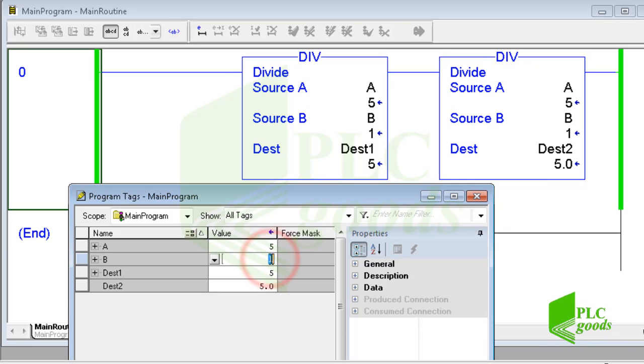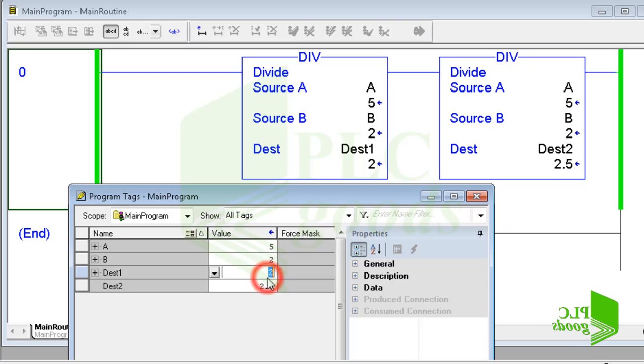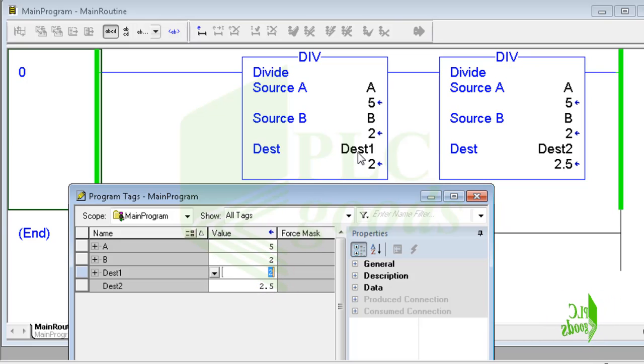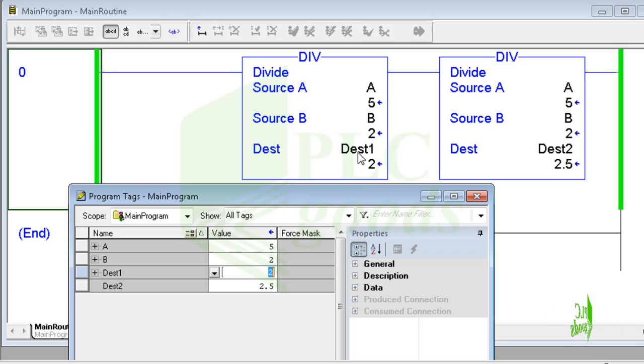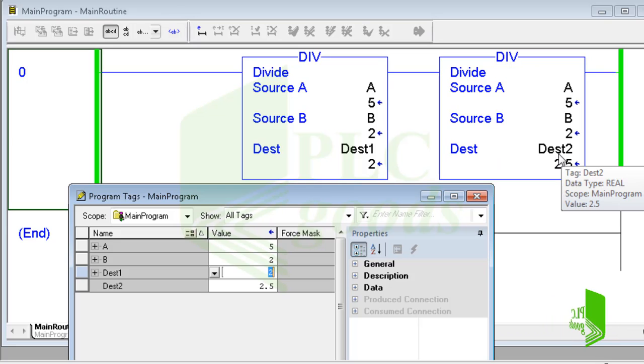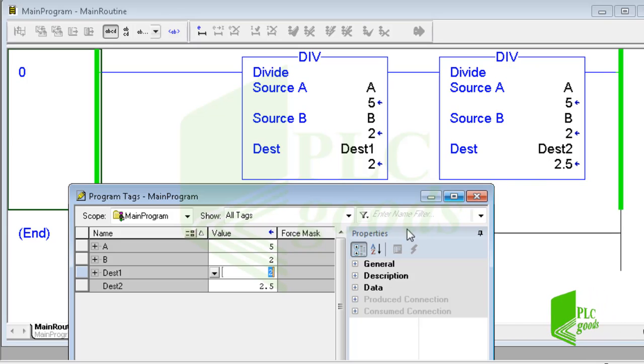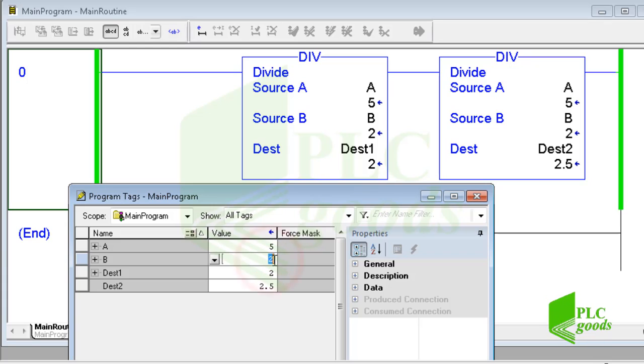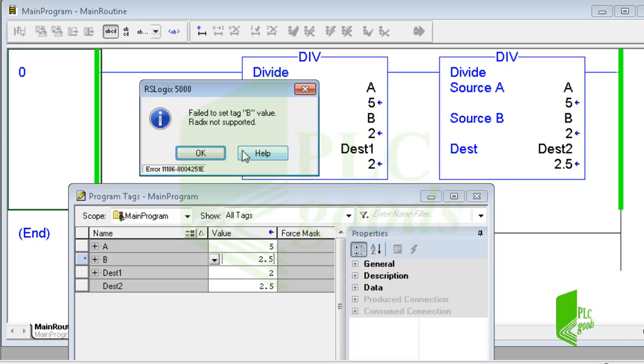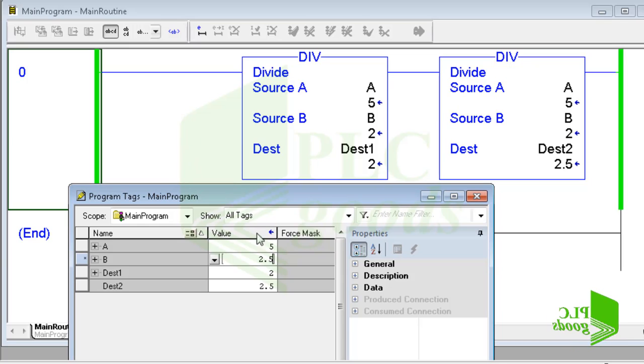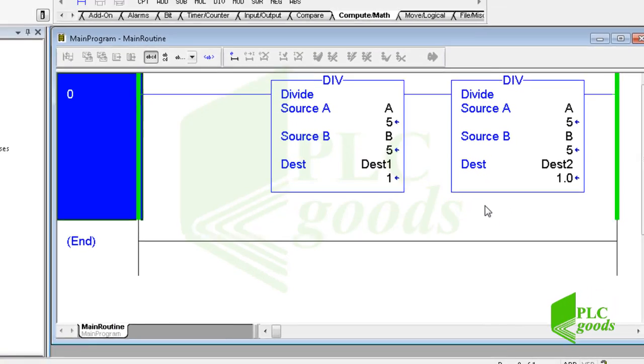Let's change the second tag again. Now here are two different results: 2 and 2.5. Because in the first division, the data type of this tag Dest1 is double integer, this data type can only store integer numbers, so the 0.5 is omitted from the correct answer which is 2.5. But in the next division the data type of this tag is real, it can store floating point numbers like 2.5. As you see I can't change the tag B value to 2.5 because its data type is double integer. So when you're using math instructions, pay attention to data type and some conditions which can cause wrong results.